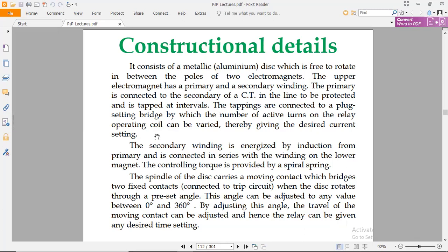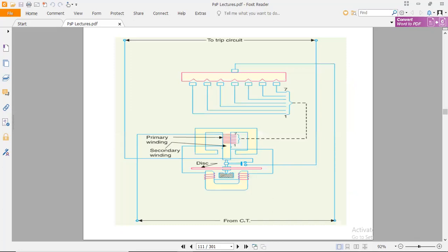The tappings are connected to the plug setting bridge, by which the number of active turns on the relay operating coil can be varied, thereby giving the desired current setting. The secondary winding is energized by induction from the primary and is connected in series with the winding on the lower magnet. The controlling torque is provided by the spiral spring, which we can see here.